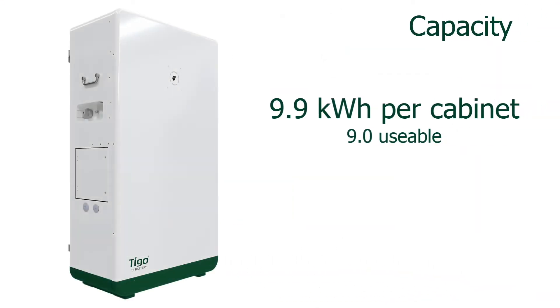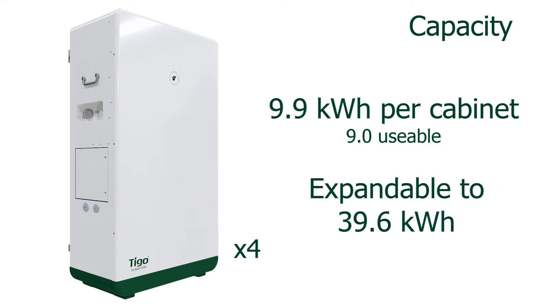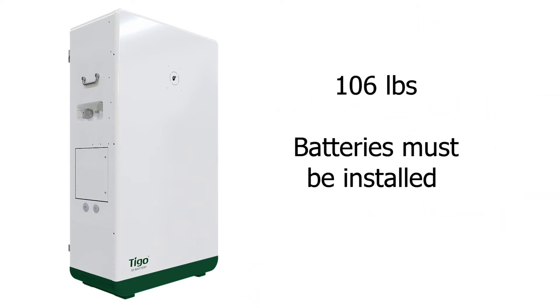The Tigo EI battery has a total capacity of 9.9 kilowatt hours to 90% depth of discharge. The system capacity can be expanded up to four cabinets for a total of almost 40 kilowatt hours. The cabinet weighs about 100 pounds and does not ship with the batteries installed.